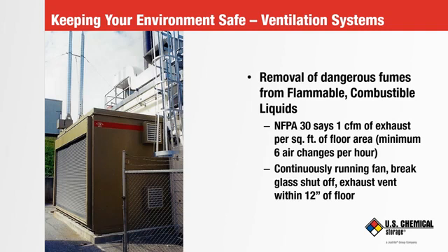During a spill, flammable and combustible liquids will flow down through the elevated floor to the bottom of a flat sump floor, spreading evenly all over the building. This provides the greatest surface area for evaporation, which will create the fume. Immediately after a spill, the liquid is exposed to the air, even before the liquid hits the floor. It evaporates and becomes a fume or vapor.